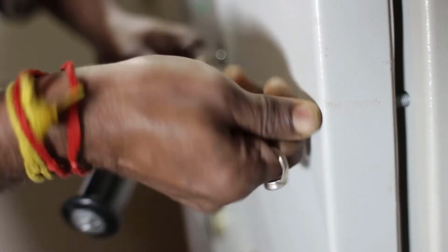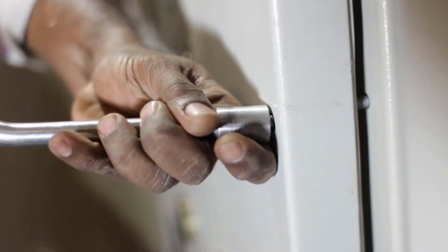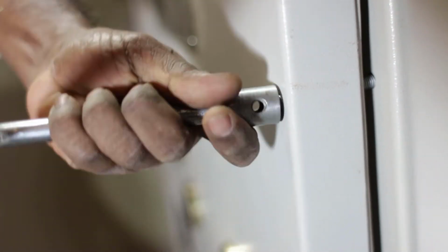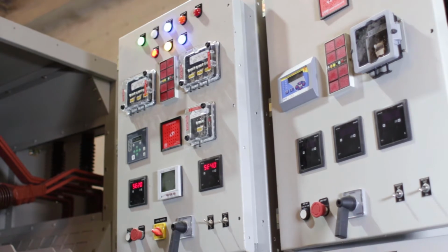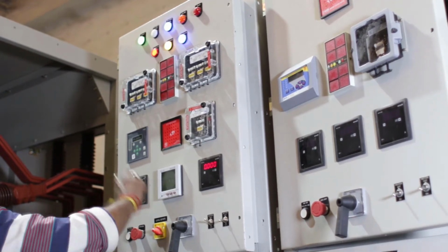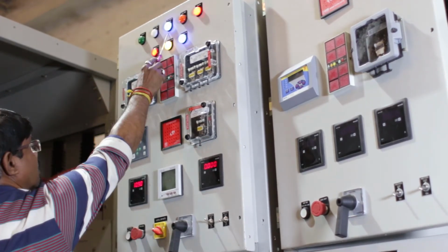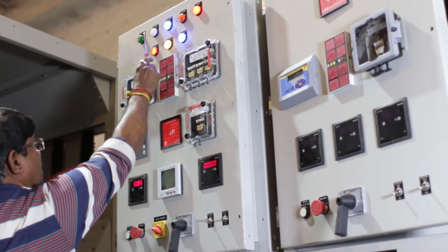Vacuum contactor panel: Siemens make vacuum contactor rated up to 11 kV is used to make vacuum contactor panel for switching HT motors at usual set. The panels are compact in size and house all measuring and protective instruments along with CT and PT and breaker power fuses.